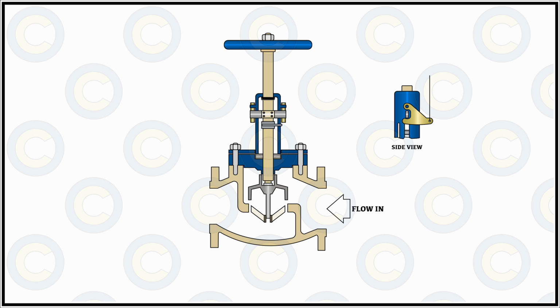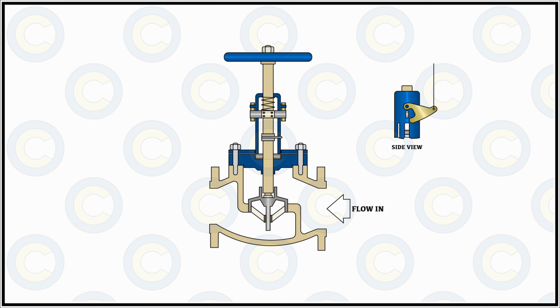So what will happen is, once this latch is displaced, leaving its original position, it makes the disc or this particular needle now free to move, and because this latch and this disc together were carrying the weight of the entire stem and the spindle and keeping the valve open, now by virtue of gravity and its own weight and the spring tension which is there on the top side, which is very important to understand, it is free to move down. And thus, under this spring force and its natural weight and the action of gravity, the valve would close.